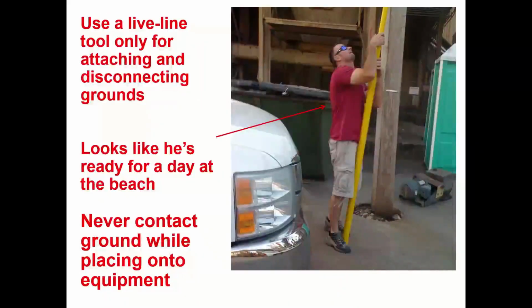This is an actual picture of a utility lineman. With grounds, you only use a live line tool, which he's doing, for attaching or disconnecting the ground. Never use your hand. If it hits fault current, adios, muchachos. And never contact the ground cable in any location or anything else while you're placing the grounds onto the equipment.